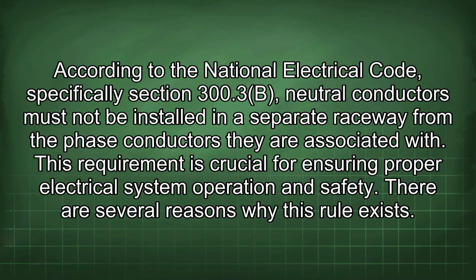According to the National Electrical Code, specifically Section 300.3(B), neutral conductors must not be installed in a separate raceway from the phase conductors they are associated with. This requirement is crucial for ensuring proper electrical system operation and safety. There are several reasons why this rule exists.